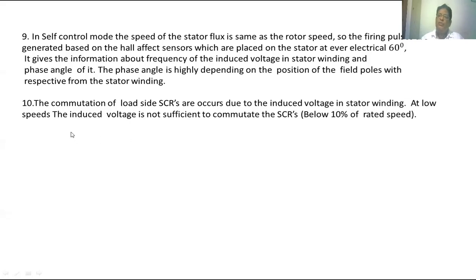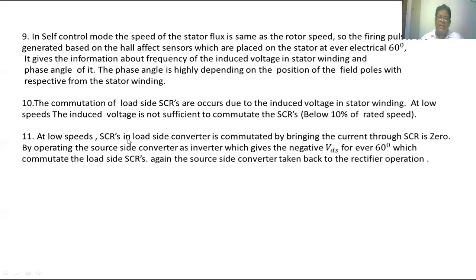At low speeds, the induced voltage may not be sufficient to turn off the SCR — approximately below 10% of the rated speed. In that case, the SCRs in the load converter are commutated by bringing the current through the SCR to zero by operating the source side converter as an inverter, which applies a negative voltage. Then the source side converter is taken back to the rectifier operation.